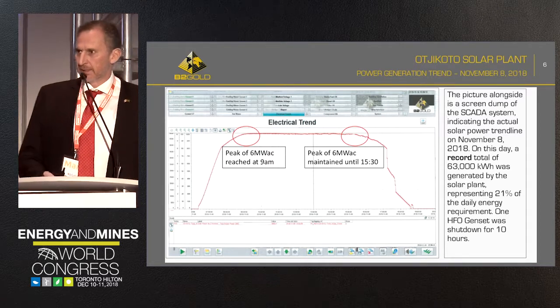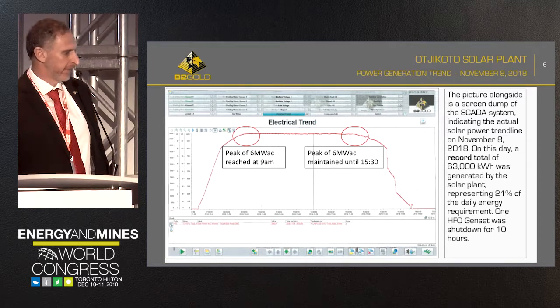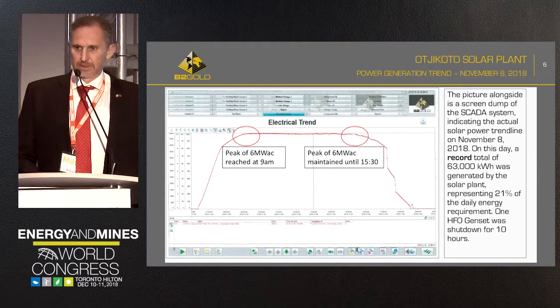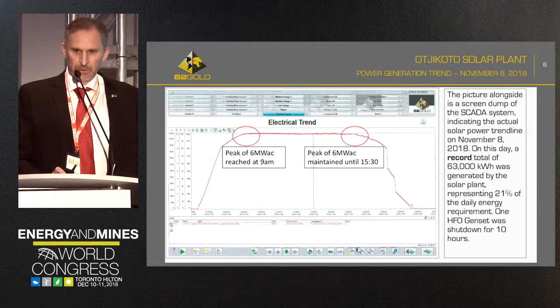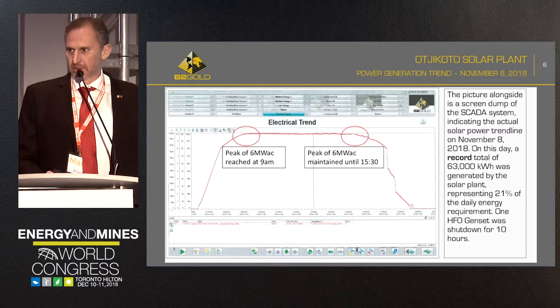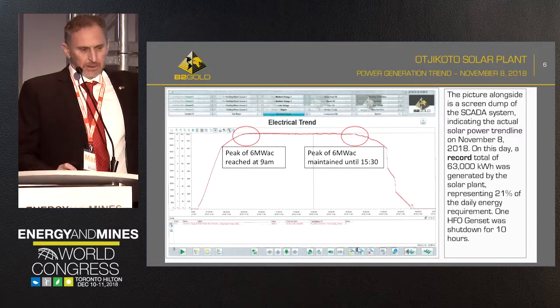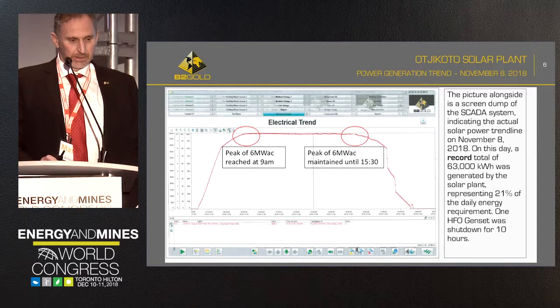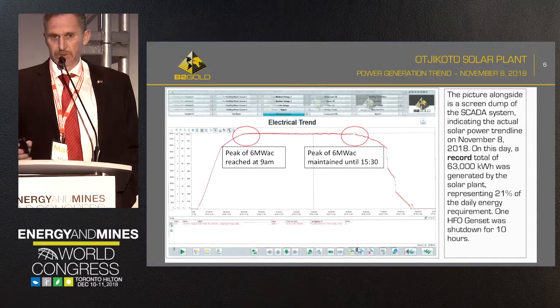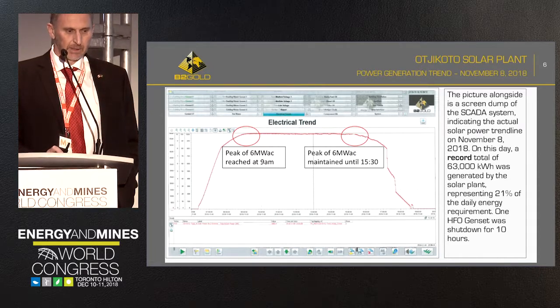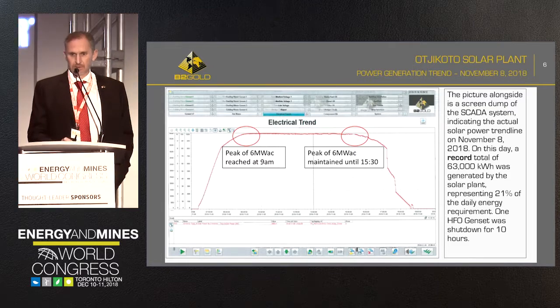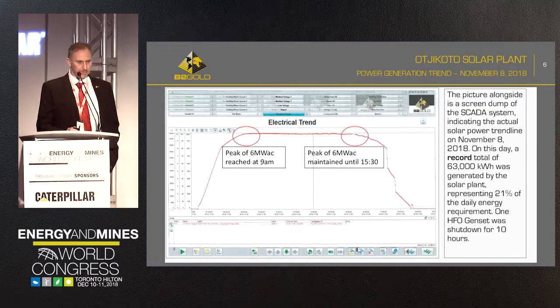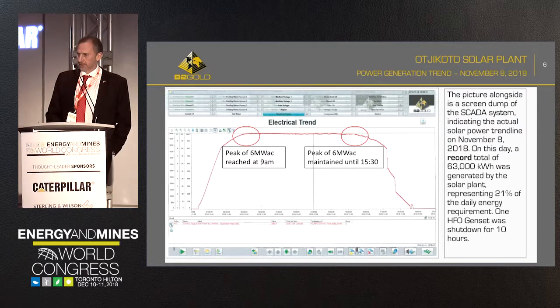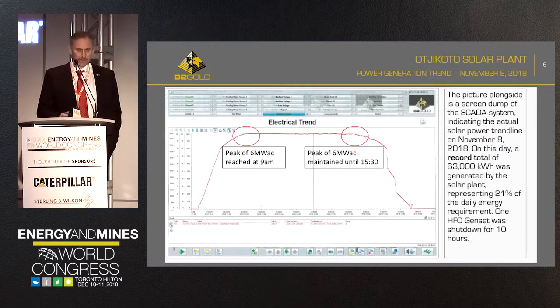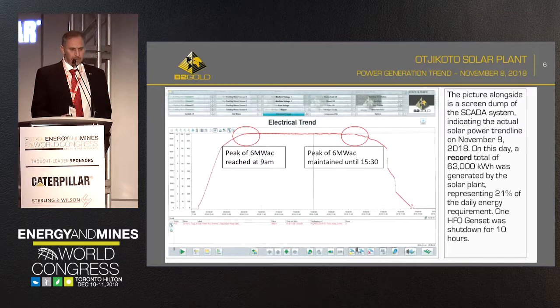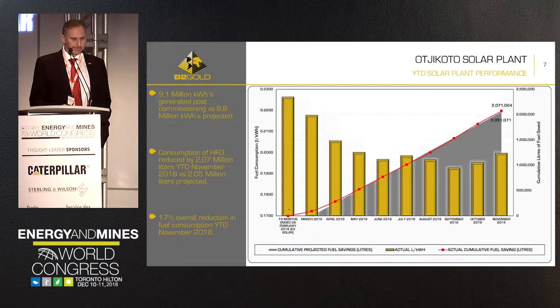If it weren't for the Cat Microgrid Master Controller—bit of a sales pitch here for you, Rob—we wouldn't be able to penetrate to that degree into our island grid. On that particular day, 21% of our power over 24 hours came from the PV plant, and an average of around 17% throughout the year comes from the solar plant, much higher than what we were told at feasibility was the maximum penetration rate possible. So it's exceeding our expectations on all levels.